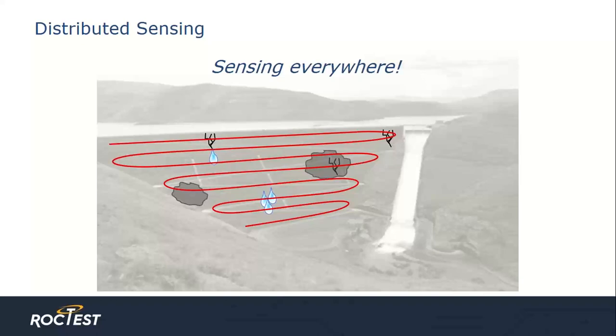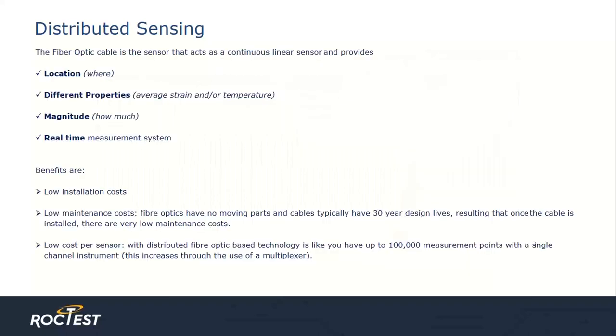Each traditional sensor requires its own signal cable and its own installation effort. The distributed fiber optic cable is a continuous linear sensor. Continuous monitoring over its entire length yields the precise location of the reading within a meter, the type of data (strain or temperature), the magnitude of these data, and the precise time events occurred. The cable has a spatial resolution of one meter, giving the end user a data point every meter. Because the cable itself is the sensor, it provides cost savings in both materials and installation. Additionally, because distributed fiber has no moving parts and is designed with a 30-year lifespan, maintenance costs are extremely low.